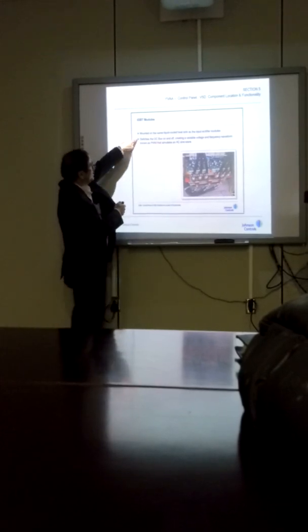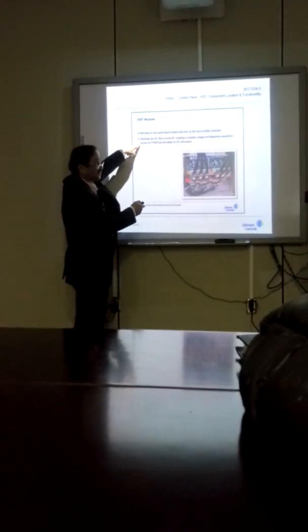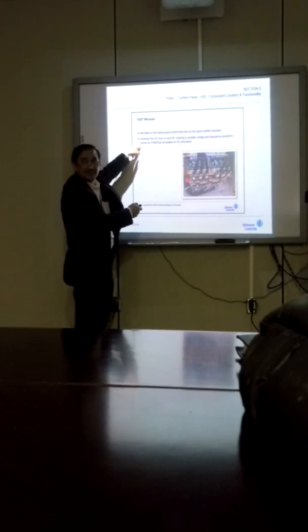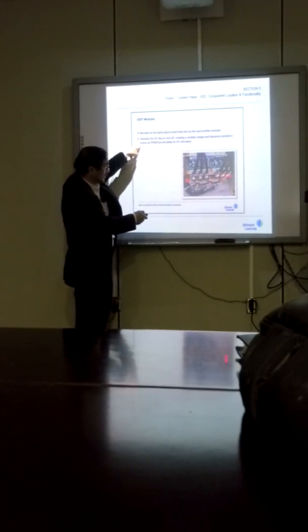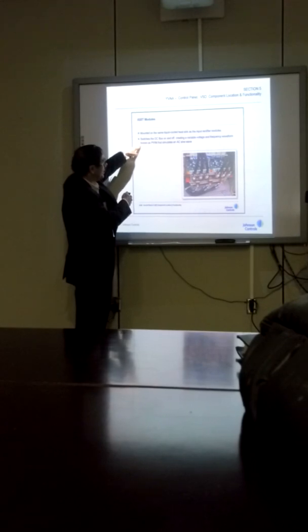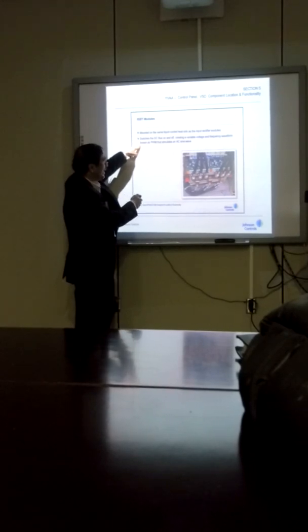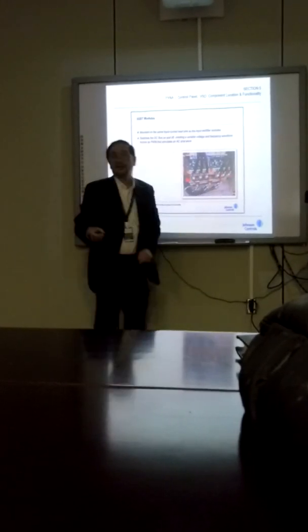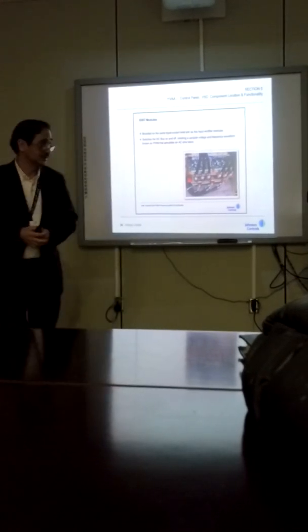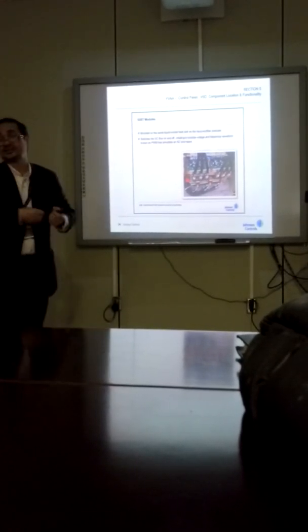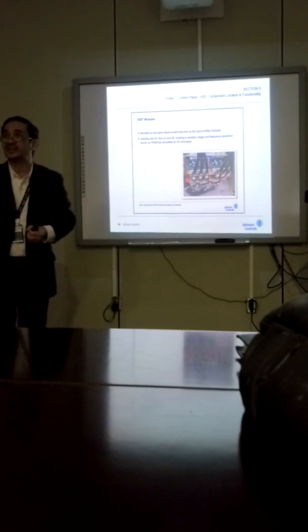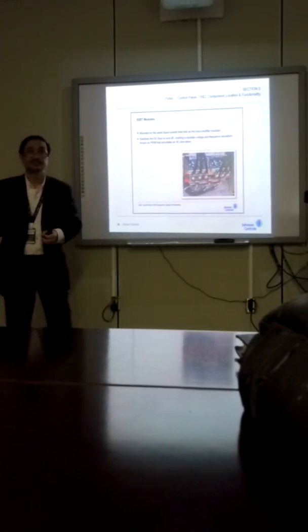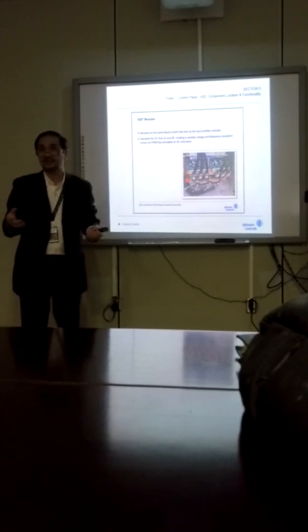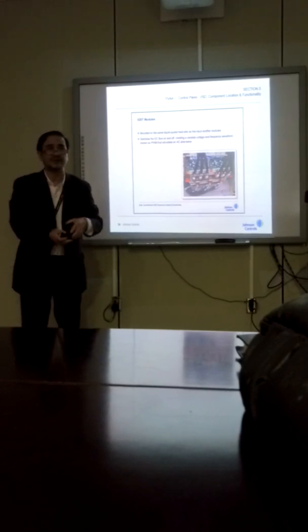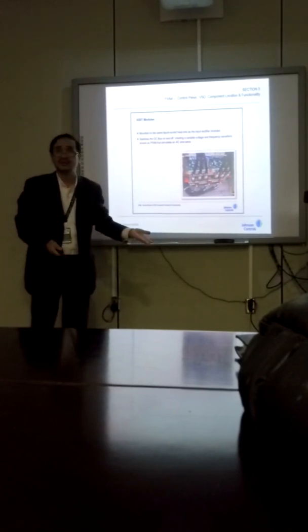This is what we said. It switches the DC bus on and off, creating a variable voltage and variable frequency to the compressor. Here's the output there. That output is this, which simulates that sine wave here. This compressor, gentlemen, our compressor is not a DC compressor. It is an AC compressor. So don't say that it's electronic control. Or how come it's AC?